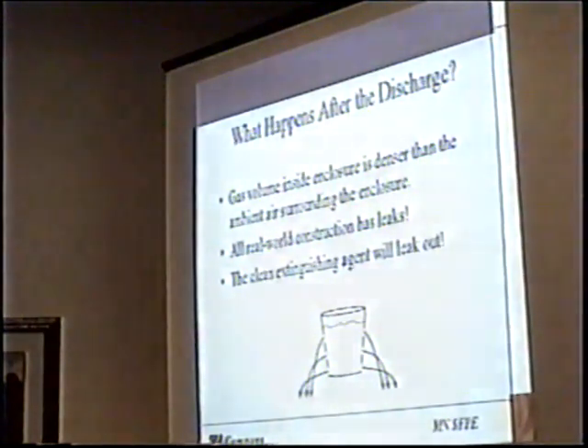So what happens after the discharge? Well, we can compare it to the leaky bucket here. Essentially, we've got a gas volume inside the enclosure that's denser than the air outside. Due to that, there's a pressure disparity due to just the hydrostatic pressure that's produced by the column of agent sitting inside of the room. And due to that, it's going to leak out. All real-world enclosures have leakages.